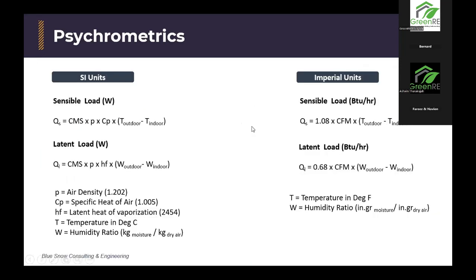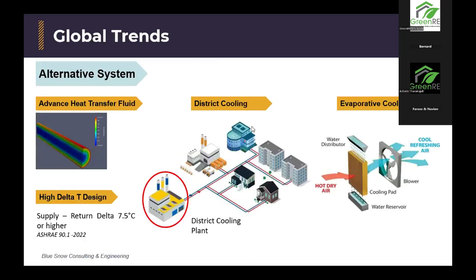So why would somebody choose to increase humidity? I thought humidity is bad. In some instances, especially textile industries, they prefer to use it because the humidity for some reason gets reabsorbed because of their materials or the chemicals they use in the manufacturing floor. Mostly textile industries use evaporative cooling. So that was something unique. And for us to design it, you need to properly understand because it's very correlated to the outdoor condition and also the movement of the air.